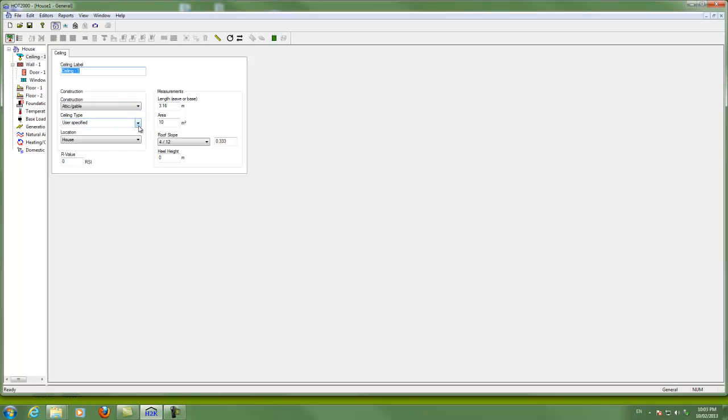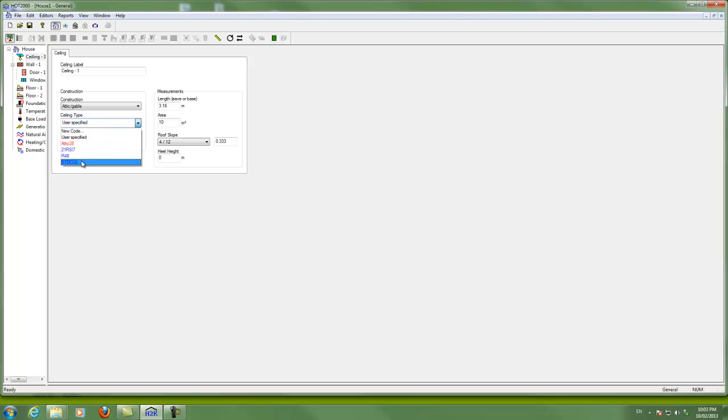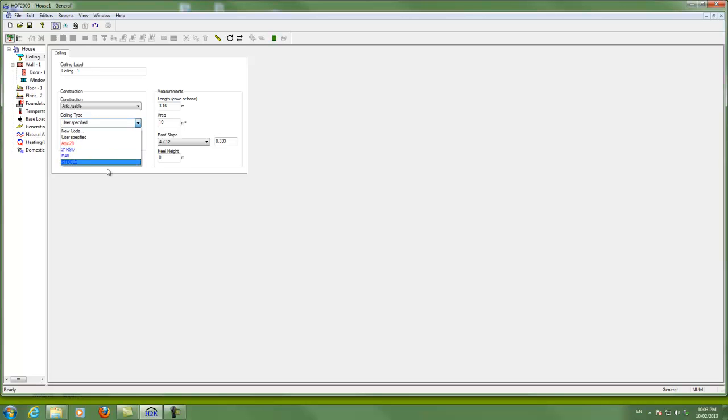So that's the construction, the ceiling type. Now this is where we're going to determine what the insulation level is and what the type of framing might be. New code means that you're going to build that from scratch. User specified means that you already know what the R value is of the assembly and you're going to enter that straight up. And these ones down here are codes for ceilings that have been created in the past, which you can just select. So once you start working with buildings and you create some new codes and you hit the same type of ceiling again, then you can just come down here and pick these.